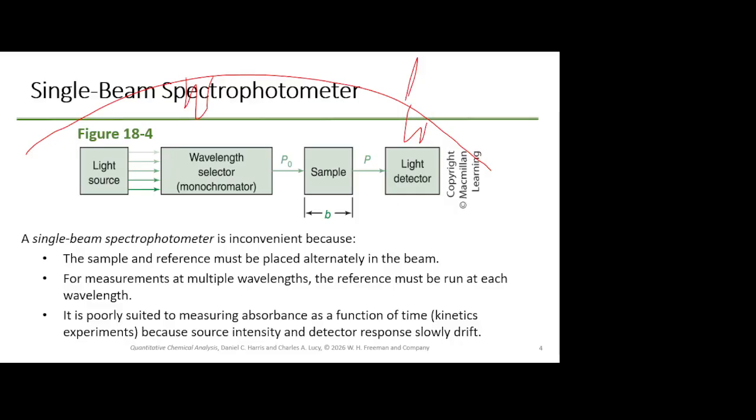Now, because the instrument changes over time, right? The instrument's going to warm up. The light source is going to warm up, so it'll slowly get stronger. Your parts are going to settle around depending on the temperature in the lab. And then you're going to also have different amounts of CO2 and water in the atmosphere, right? And so what was happening here is those effects, these were the CO2 and water changing in the lab. And then this right here is actually your instrument changing.